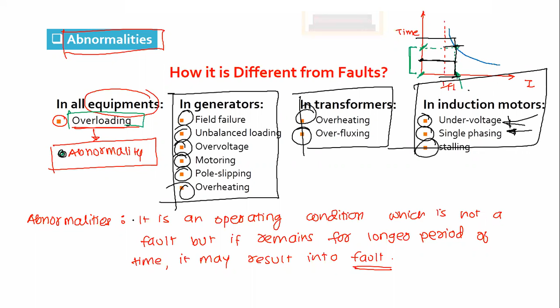Similarly, stalling. In a transformer, overheating, overfluxing. In a generator, field failure, unbalanced loading, over voltage, motoring, pole slipping, overheating. All these are not faults. They are abnormal operating conditions, and the machine can operate for a certain period of time depending upon the design. But if it is operated beyond a certain period of time, it may result in a fault and can damage the equipment. So is the difference between fault and abnormal operating condition clear?